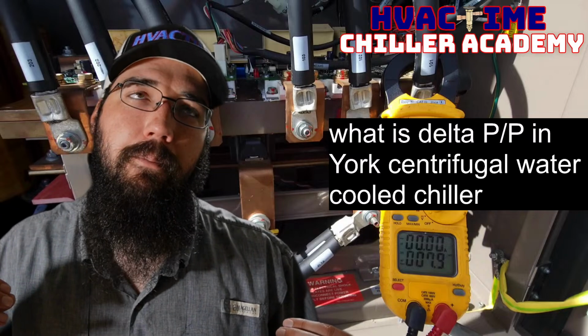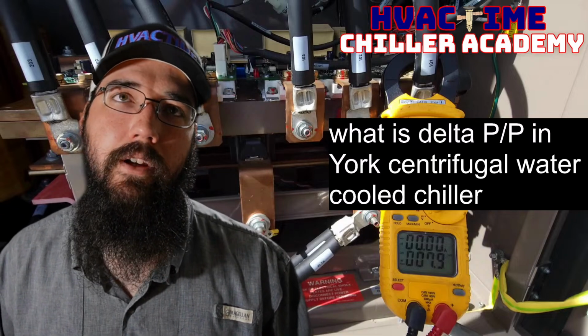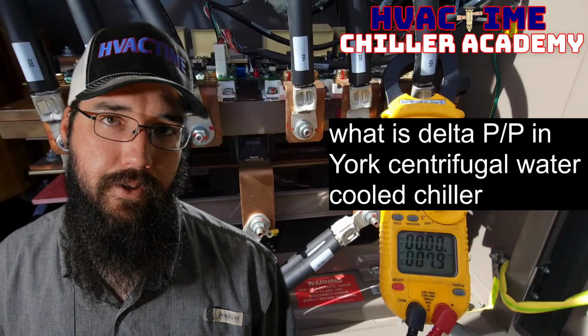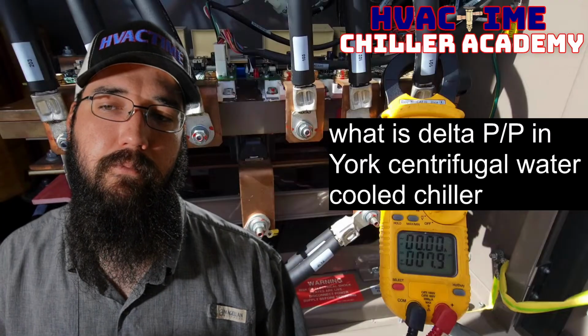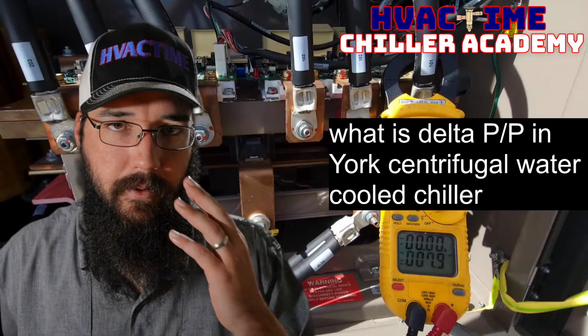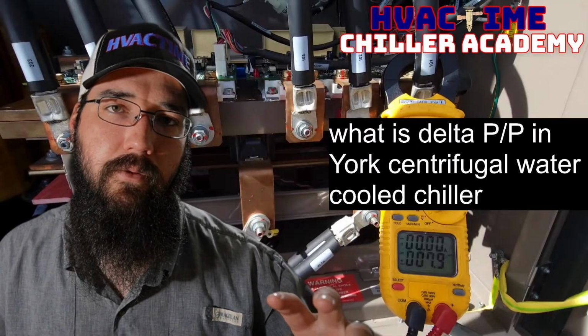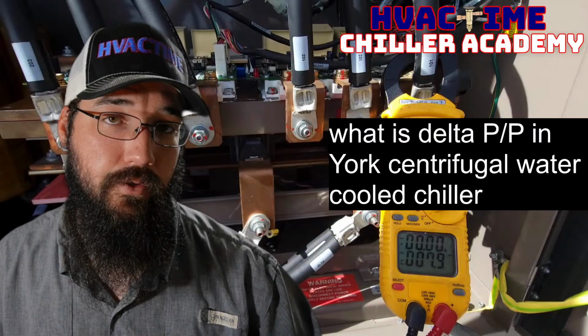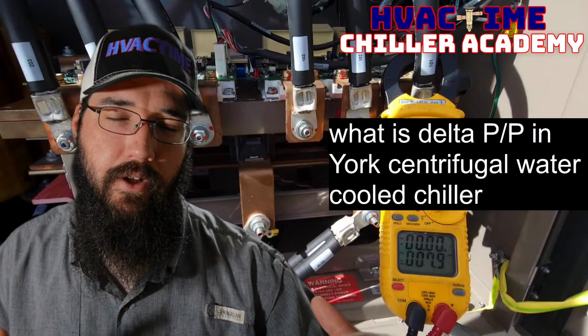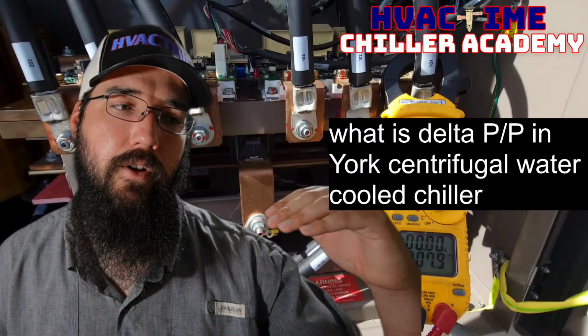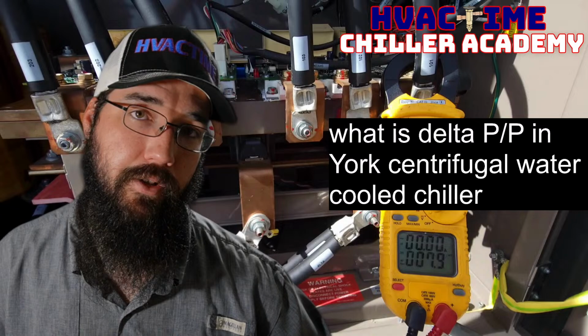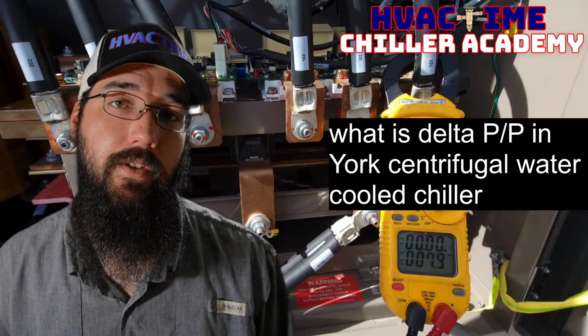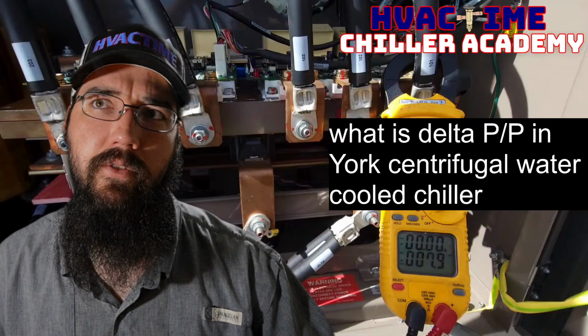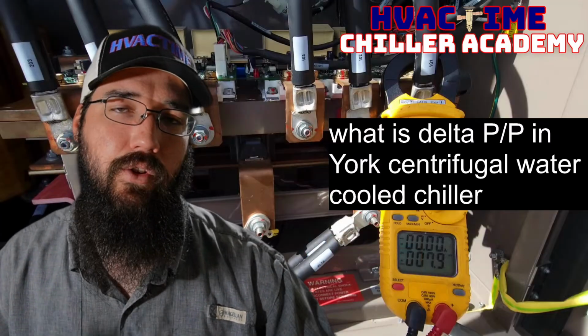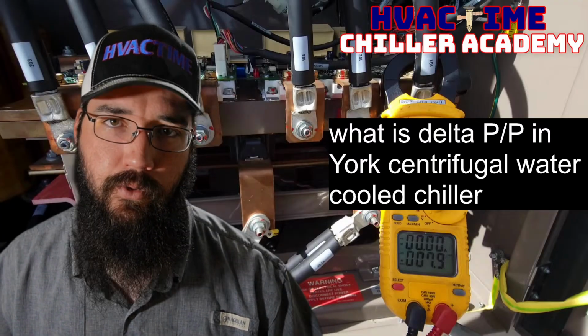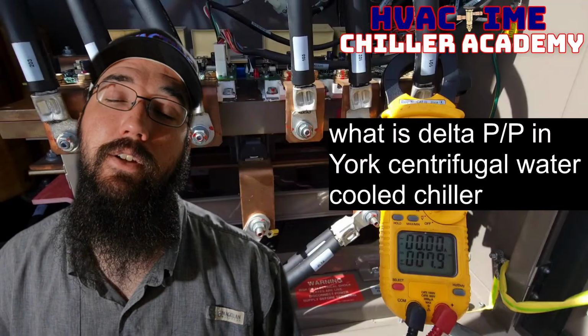Now, I'd have to verify. I don't remember if York is actually taking proper compression ratio or just a raw literal delta P over P, because proper compression ratio is taking your absolute pressures. So you're taking your pressure reading inside the chiller, and then you're converting that via your atmospheric pressure wherever you're at. For me, I'm fairly close to sea level, so I use 14.7. You add that to the gauge pressures that your transducers are reading, and then you divide those into one another. That gives you compression ratio.